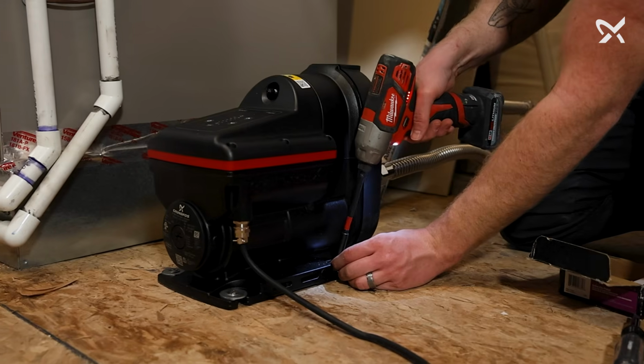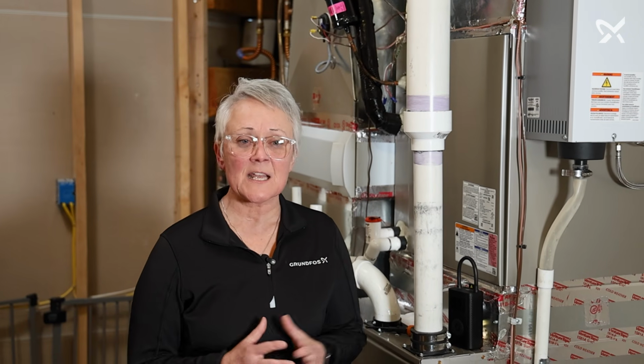So the next thing we want to do is make sure that we have mounted our SCALA securely to the floor. Now you can use vibration pads in this installation, and we recommend that you do, because anything you can do that can control this vibration will reduce the amount of sound that's being transmitted through the piping and could potentially cause notice by the homeowner. So we want to control that as much as possible. Mount it directly to the floor though, because when the pump comes on, it creates a lot of thrust. And that thrust, if you're hard piping, can damage the connection piece if the pump is not secure.